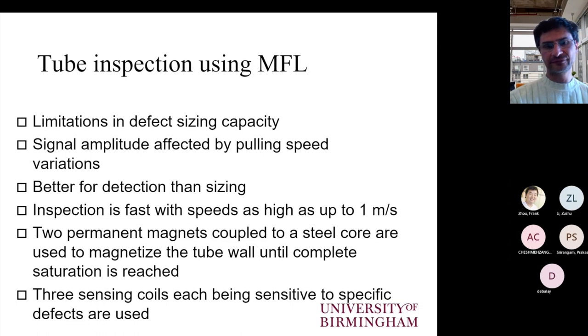And the effective instrument is based on two permanent magnets, which are coupled to a steel core, and then they are used to magnetize the sample or the tube wall until saturation is achieved, and then any flux leaking will be what will be detected. In tubes, we have to use three sensing coils.